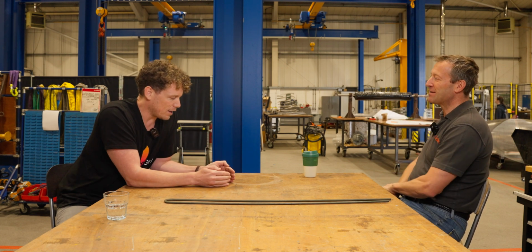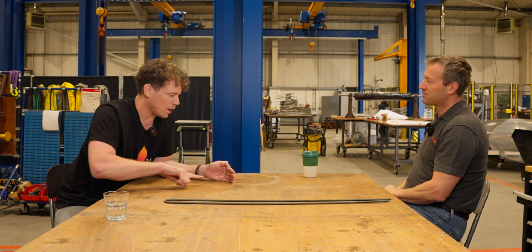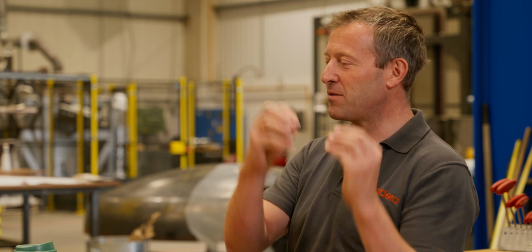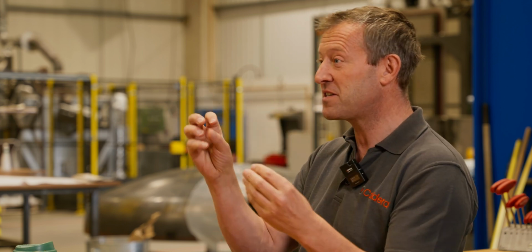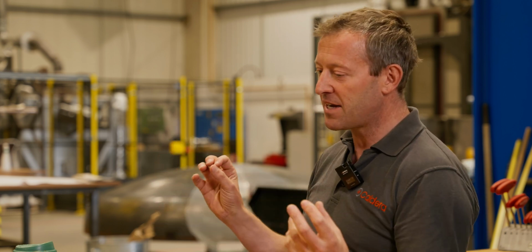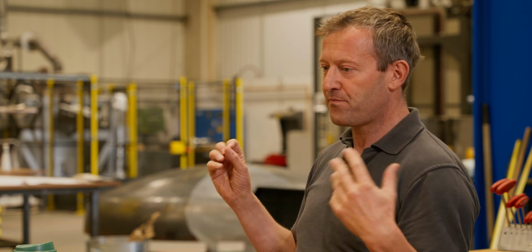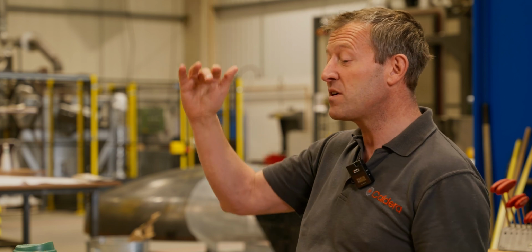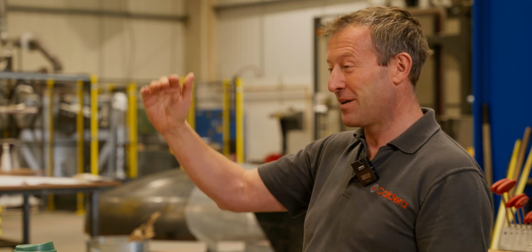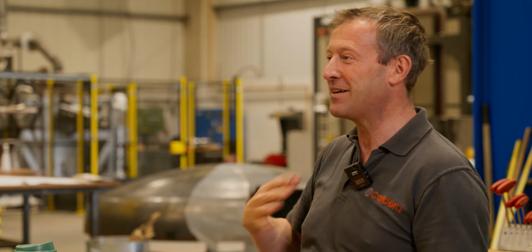That's our capping point. And that's full, always full at that point. And it turns off. And then we're using water or steam to extract back out to use at point of use. We're using the boiling process to take the heat out. Right, okay. So you don't need very much water to convert to steam to extract a huge amount of power. So we use that to take it out, and then we cool the blocks down, and in our current design, about 250 Celsius, we call them empty. So they're still very hot, but from our perspective, that's empty.